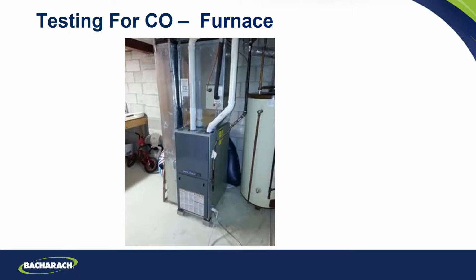So when I was up there, I checked it out, and here's the end of the story. They did everything I told them: cleaned the burners, checked the linkage, but they were new. They said there was no flame impingement. They checked the draft and checked the gas pressure. Well, it was flame impingement. One of the burners was just slightly cocked, so you couldn't see it, and it was touching the Morrison tube and made a flame impingement. I took up my bigger analyzer, and it showed around 8,000 parts per million. So you definitely want to check those things.